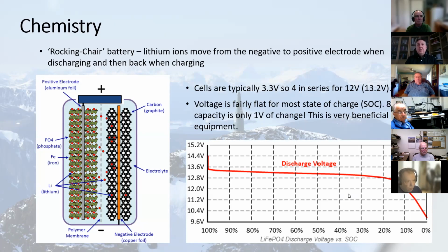So you can see in the diagram here, you have the carbon or graphite layer. Under load, these lithium ions are moving into the phosphate layer, and then under charge, they reverse that process. And it's a pretty simple process in each direction. As a result of how that works, they're inherently very efficient, and the discharge voltage curve is also very stable. So you can see here a graph of a typical lithium iron phosphate. Generally, lithium iron phosphate comes with a group of four 3.3 volt cells to produce your 12 volt equivalent cell. And at full capacity, they'll be around 13.4 volts.